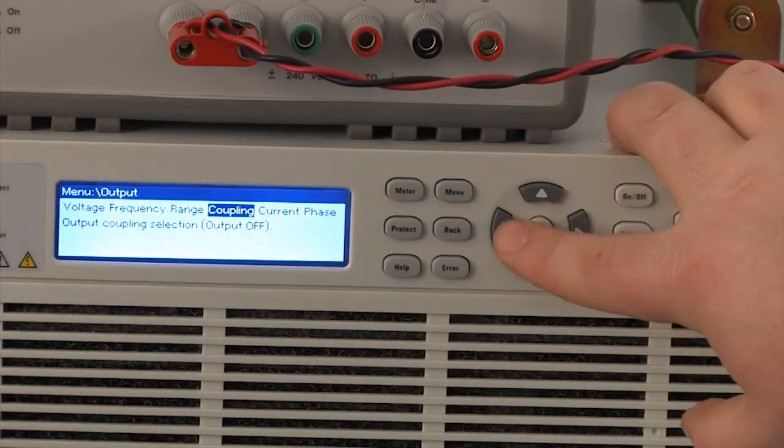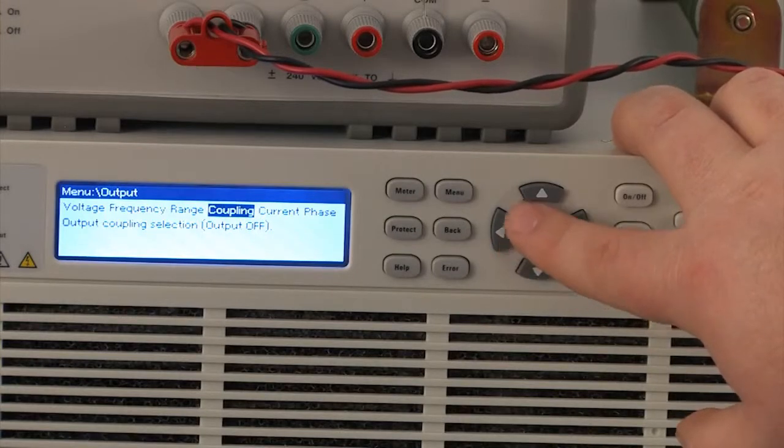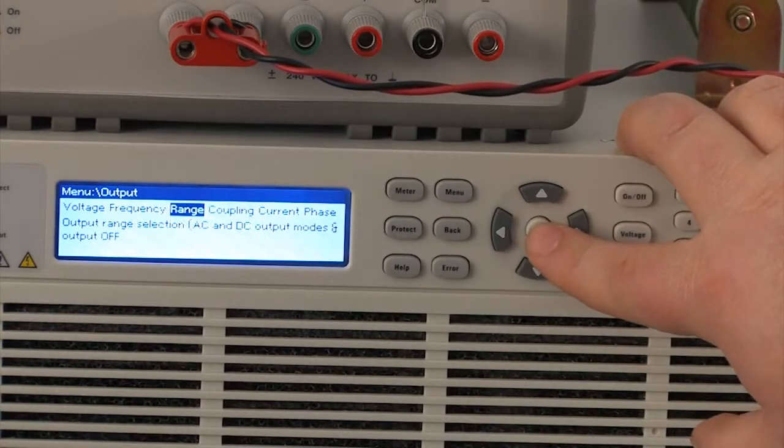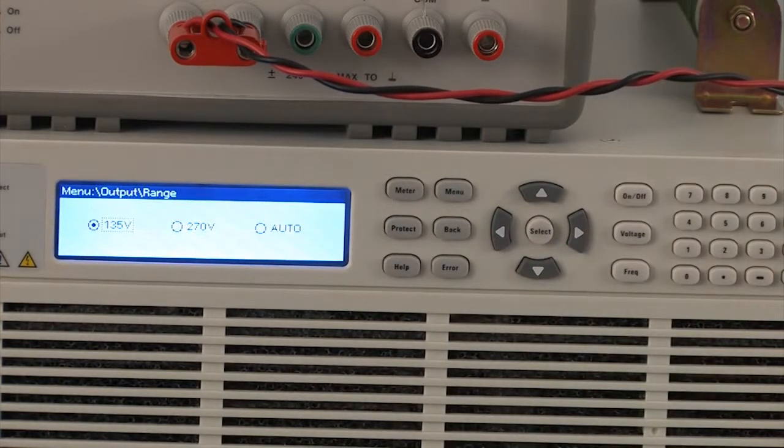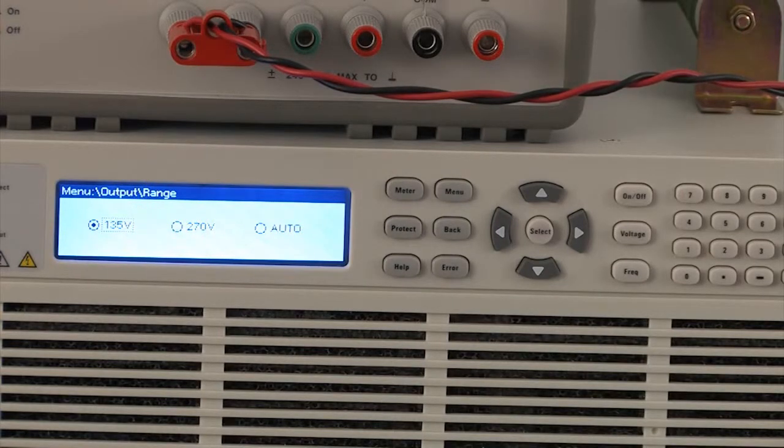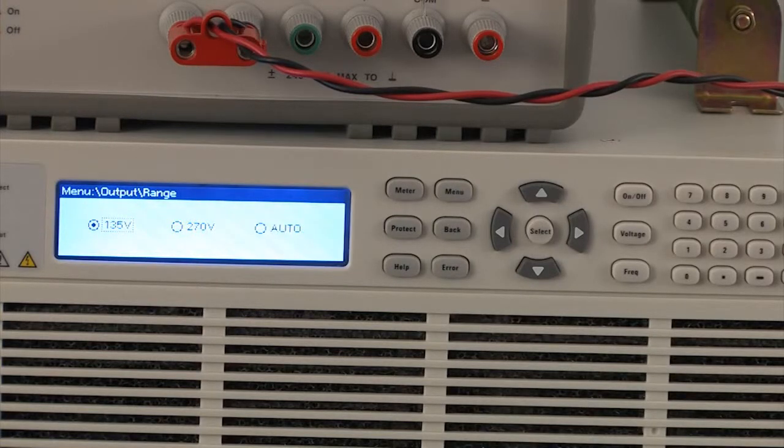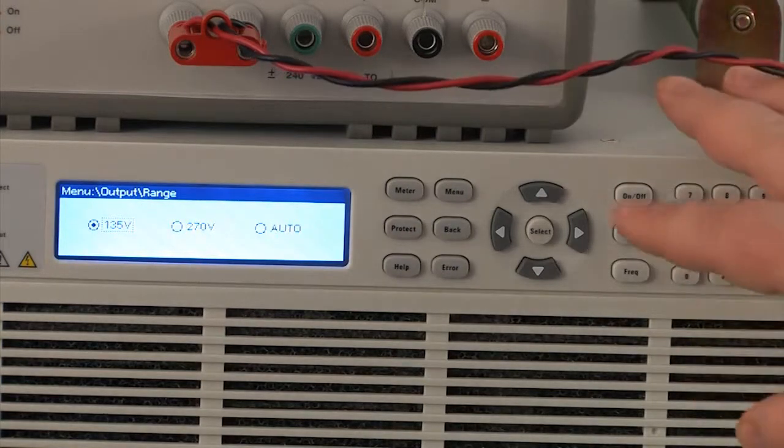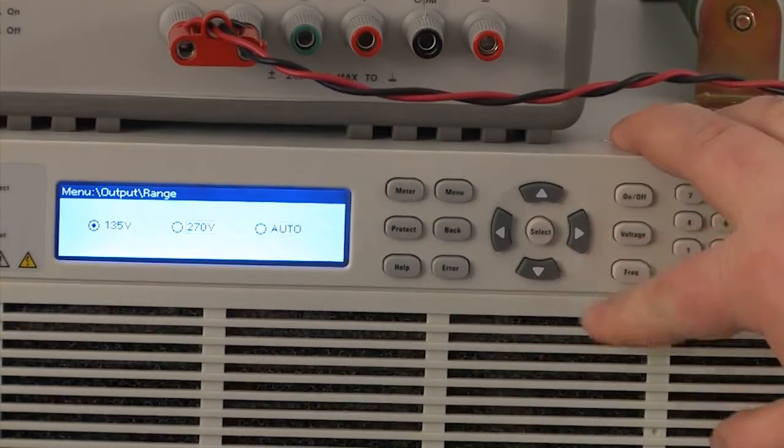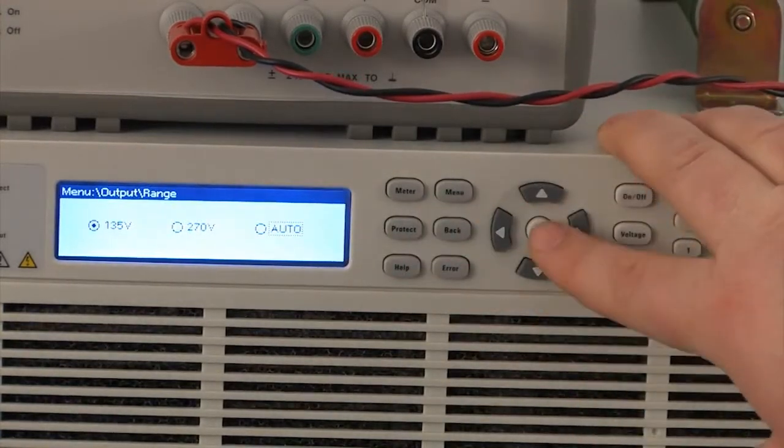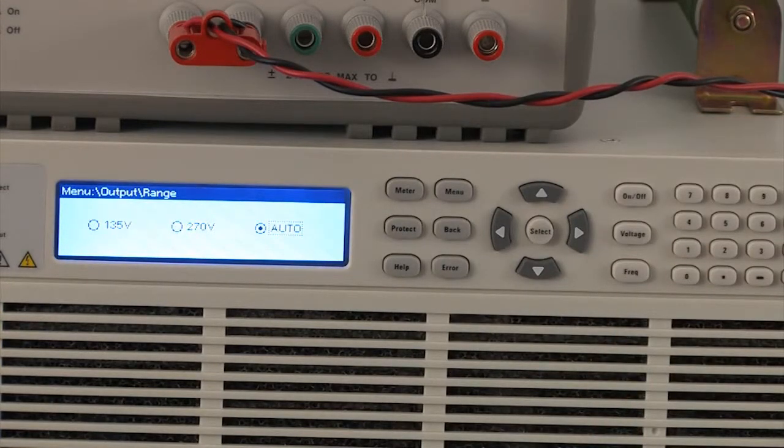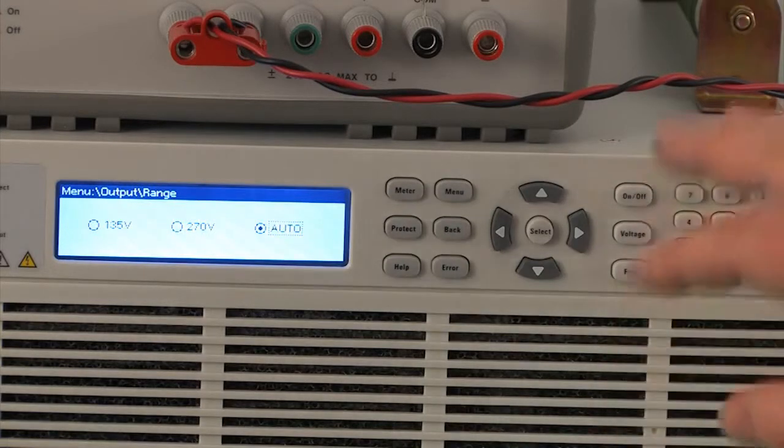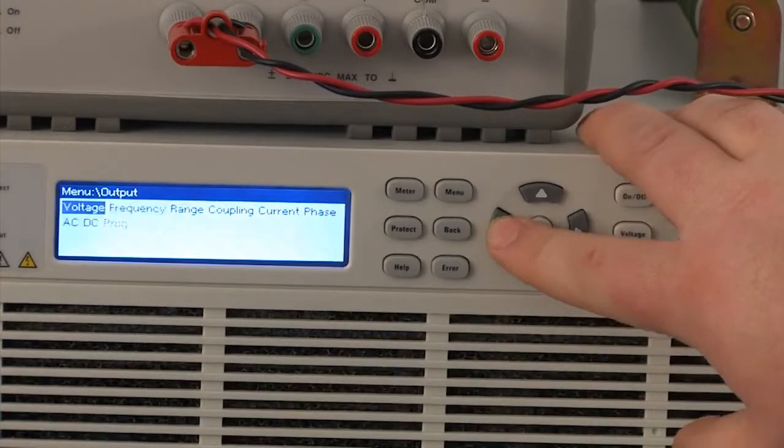And another feature that is pretty interesting is there's a range for output programming voltage. You can see that there's two different ranges. There's the 135 volt range and the 270 volt range. So you're going to want to use the 135 volt range for 120 volt testing, 100 volt testing, and 270 volts used for 240 volt testing and 230 volt testing. But another nice feature is that we have this auto range. So when you choose auto, it will actually choose the correct programming range for you based on your output voltage setting.